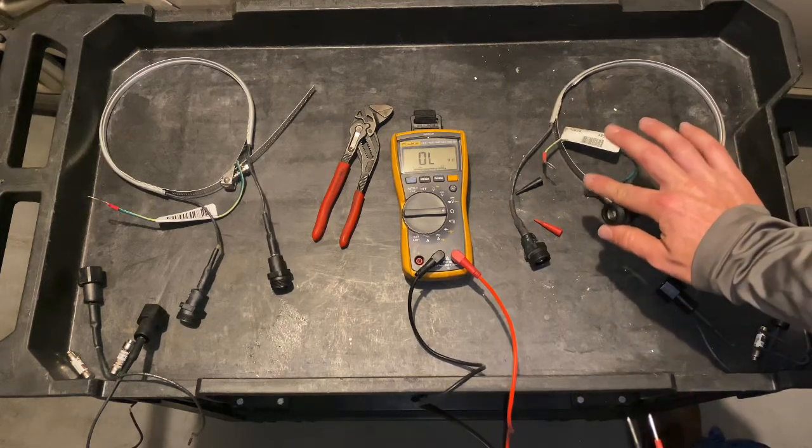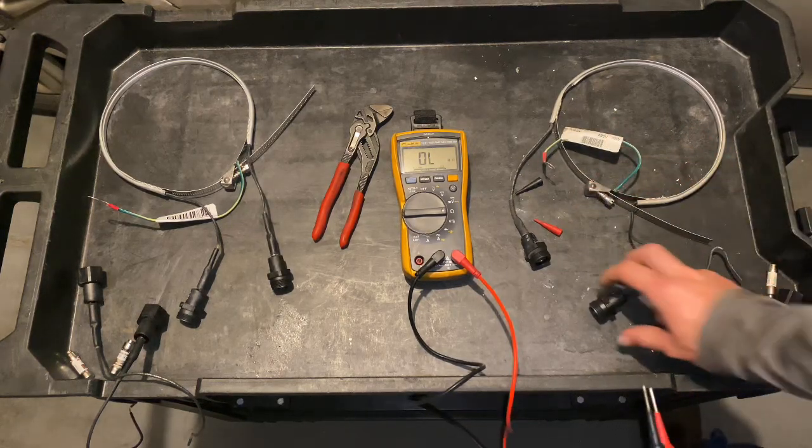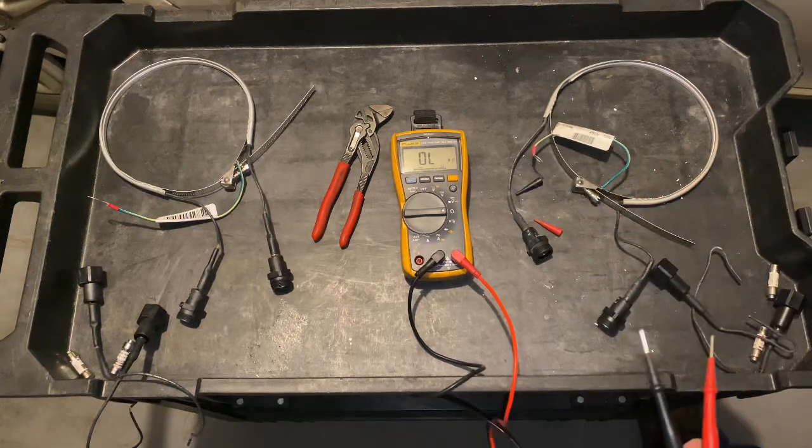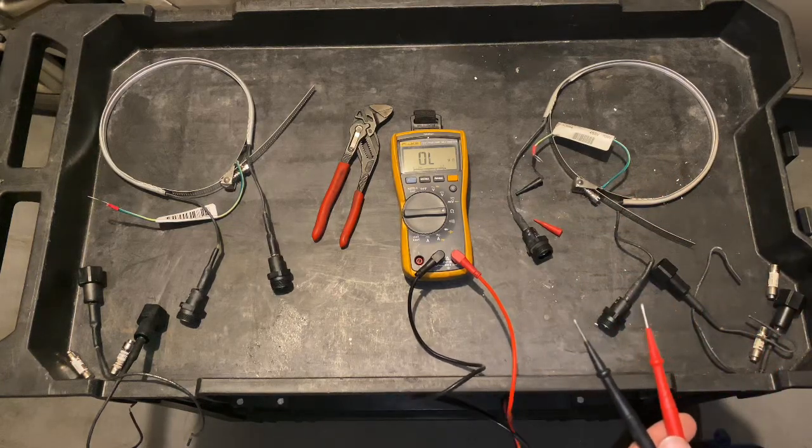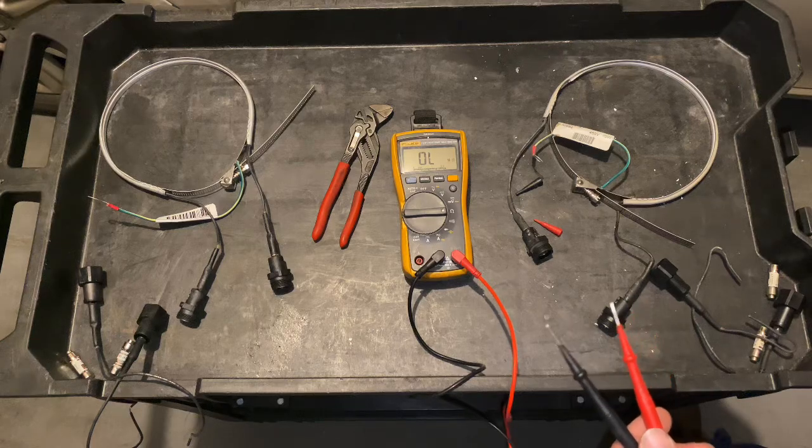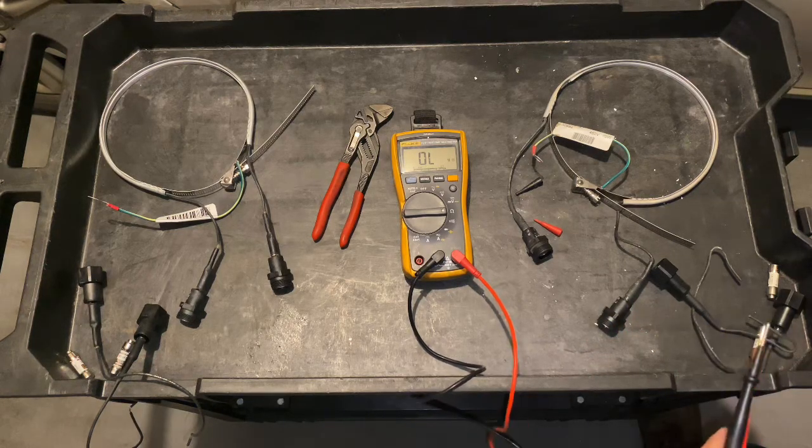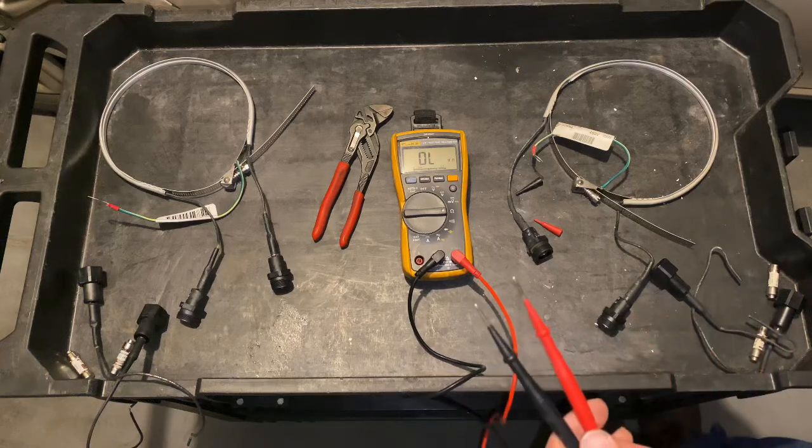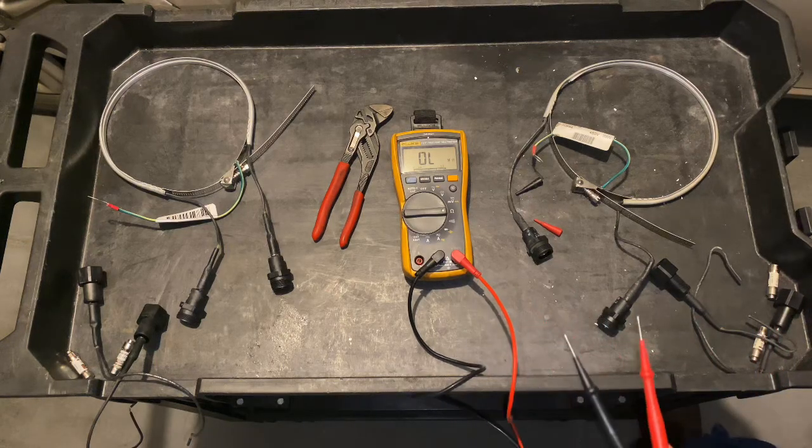Again, you need to remember to take the fuses out and check them right at the element like this. Otherwise you're going to get a resistance value even if they're open, which I can't quite explain why that is, but that's what I've seen.